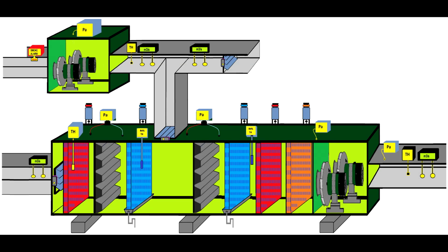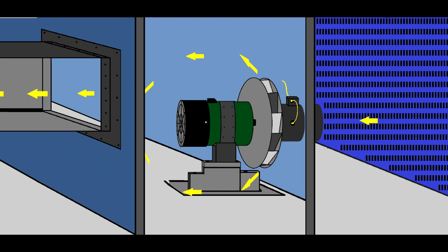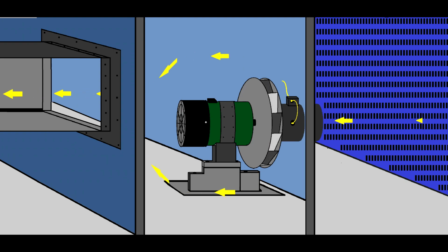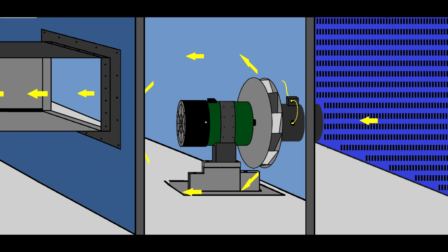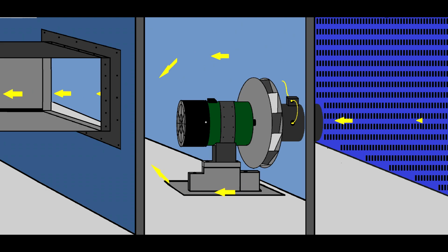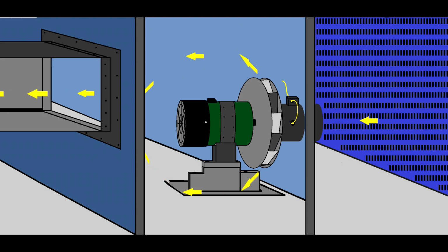Maybe you're asking yourself, what is the pressurization unit and why am I seeing an air handling unit on the screen? Well, my dear friends, the air handling units are using heat exchangers to control the air temperature, and some of these heat exchangers are using boilers to heat the heating agent and to control the pressure in a heating installation, sometimes using pressurization units, unlike in a domestic application where we can pressurize the unit manually. In a commercial environment, we have to make sure that the heating system's pressure is monitored.